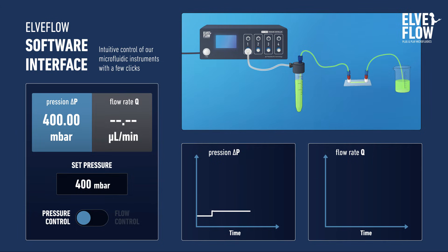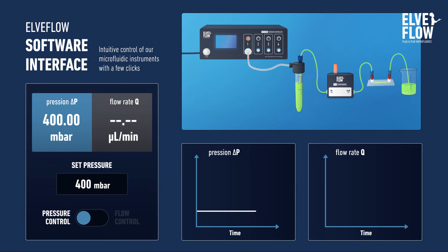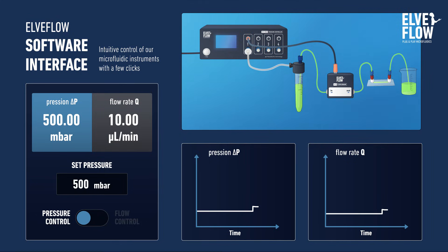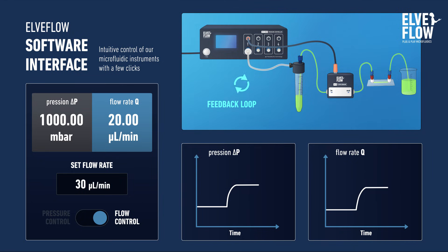A pressure-driven flow controller only provides direct access to pressure. To access flow rate values, one needs to add a flow rate sensor to the setup. Combining a pressure flow controller and a flow sensor offers the advantage of working in either pressure control with flow rate monitoring, or in flow rate control with the inlet pressure automatically adapting to reach the target flow rate. This is achieved through a feedback loop between the flow sensor and the pressure controller via the control software.